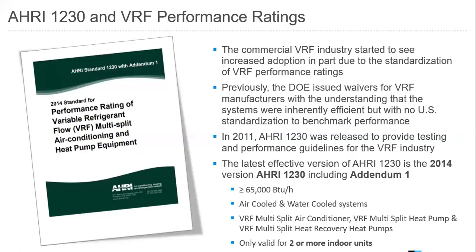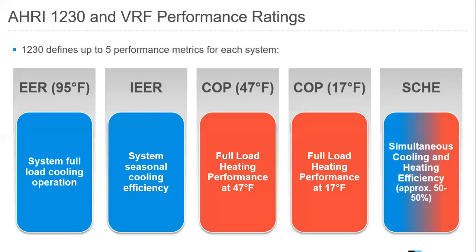And then for systems larger than 5 tons, AHRI 1230 defines the performance requirements for VRF systems. In 2011, AHRI 1230 was released to provide testing and performance guidelines for the VRF industry. The latest version of AHRI 1230 is the 2014 version, which includes Addendum 1. And this covers the air-cooled and water-cooled VRF systems. 1230 defines up to 5 performance metrics for each system.